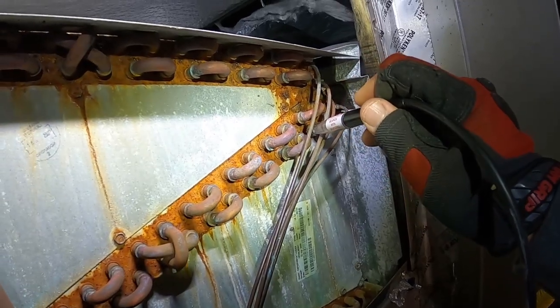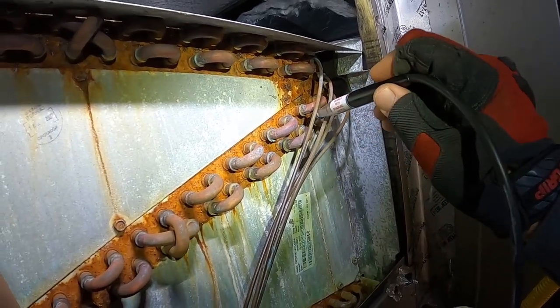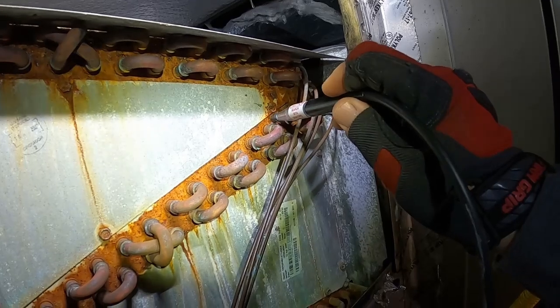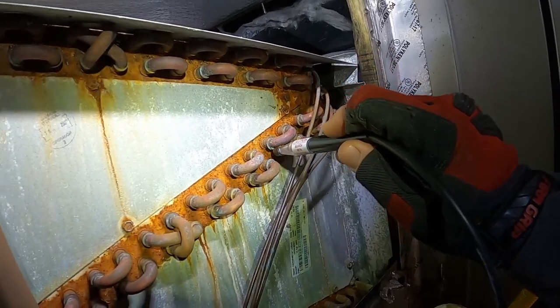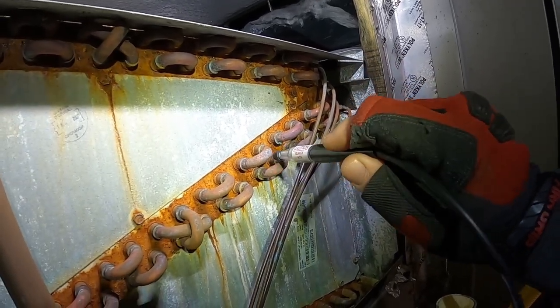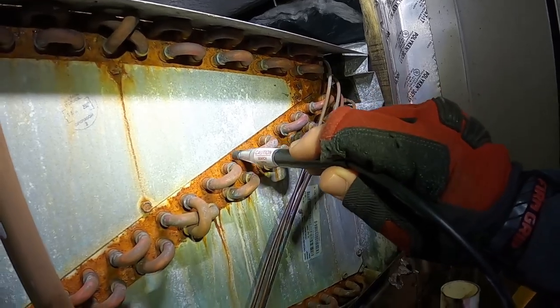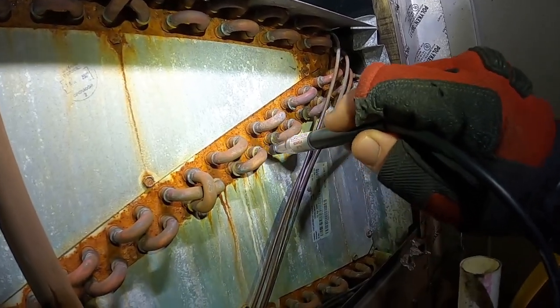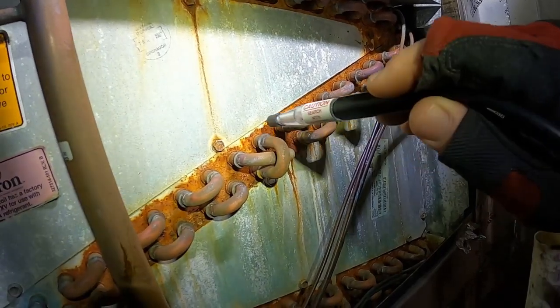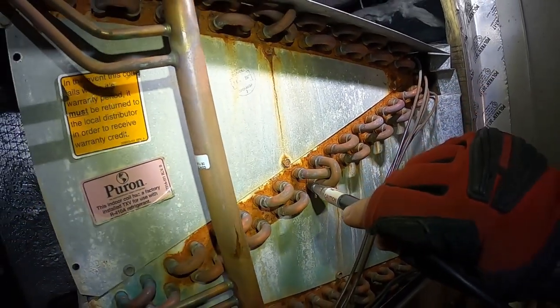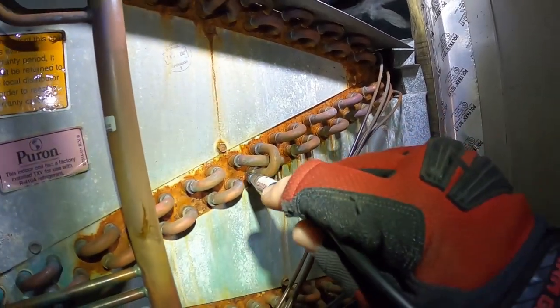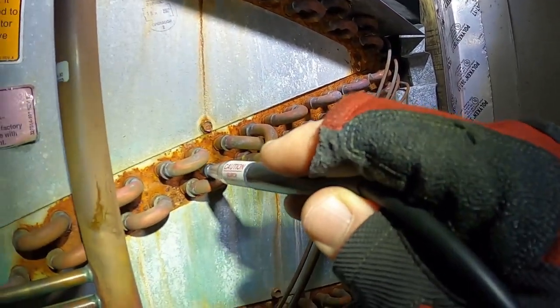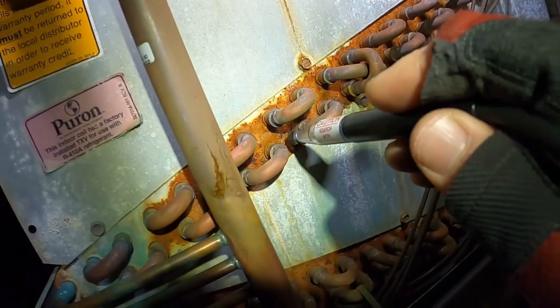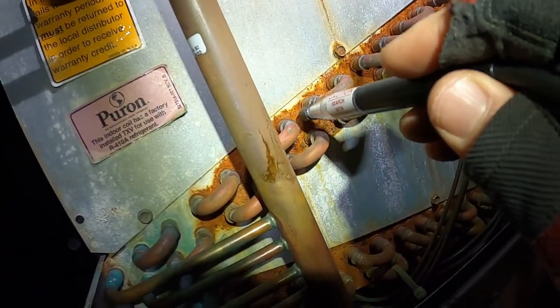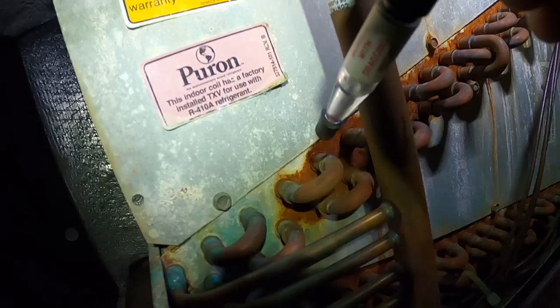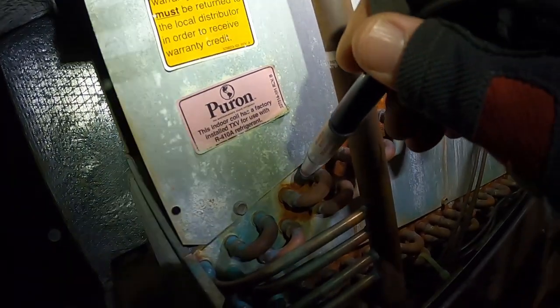That's the thing about these old copper coils - rust doesn't always mean there's a leak. Low charge does, but it could be in the condenser coil out there. Those will sneak up on you and bite you once in a while. You just always assume you have a coil leak on the evaporator, and you end up finding a pipe rub or a leak in your condenser coil.